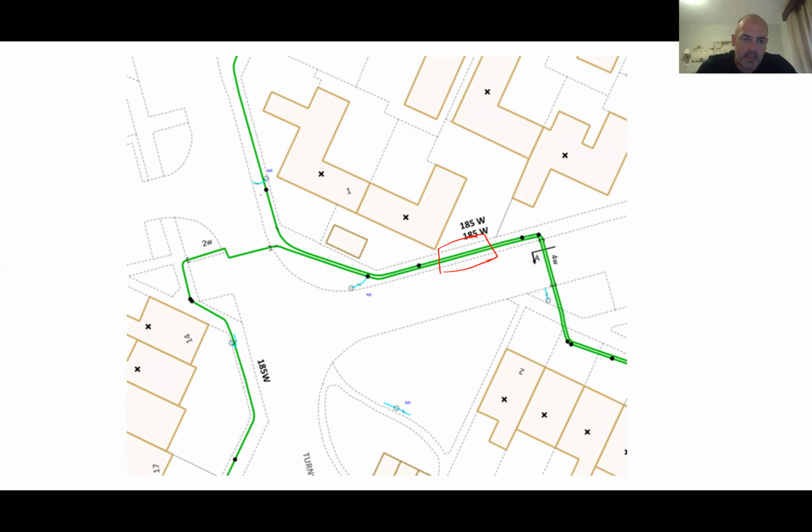And what I can see is separation. So for example, I can hook up to the column here with my genny and trace the top cable and mark it. And then I could go over here and hook up to this one, and I could locate the bottom cable. So I found both those cables by understanding where to apply the transmitter.